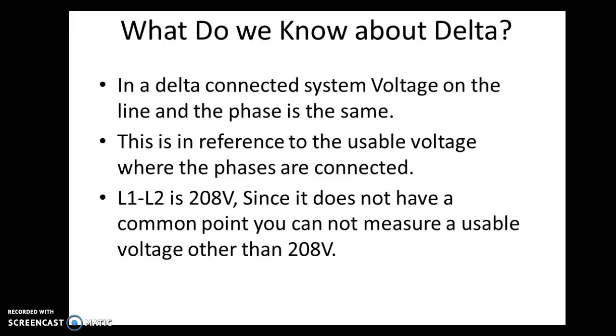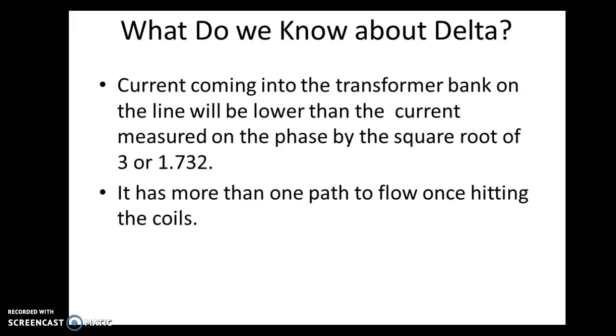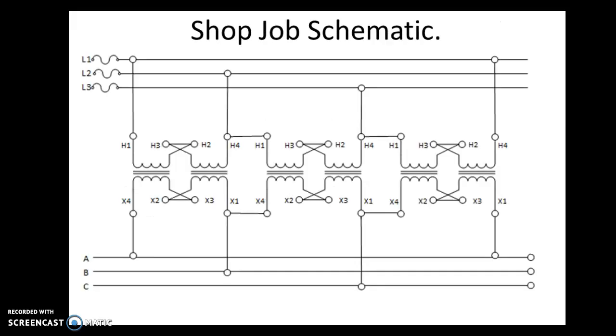One scenario where you might see a different available voltage is if you create what's known as a high-leg delta. In our system, we're going to see 208 between line 1 and line 2, and we also know that current coming into the transformer bank will be higher on the line than it is on the phase by the square root of 3. The reason for this is because once it gets to the transformer's coils, it has more than one path back to the source, unlike the Y connection.